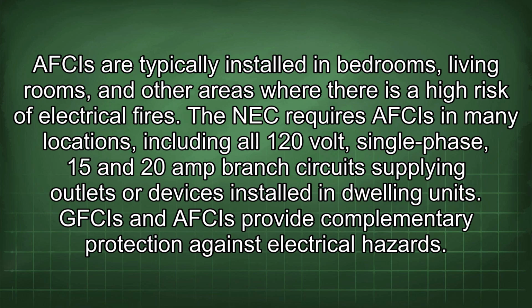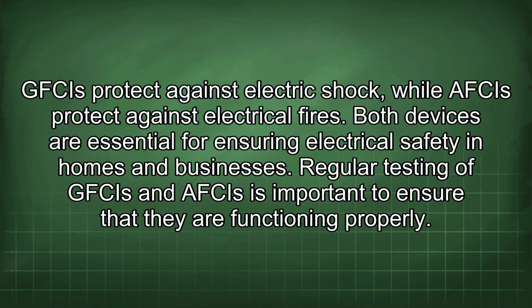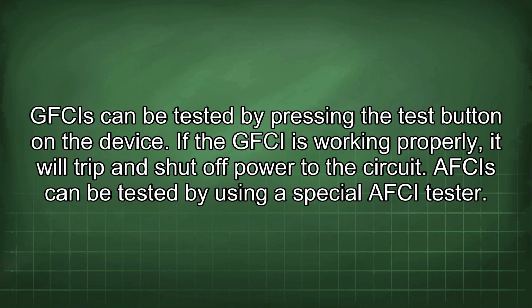GFCIs and AFCIs provide complementary protection against electrical hazards. GFCIs protect against electric shock, while AFCIs protect against electrical fires. Both devices are essential for ensuring electrical safety in homes and businesses. Regular testing of GFCIs and AFCIs is important to ensure that they are functioning properly. GFCIs can be tested by pressing the test button on the device. If the GFCI is working properly, it will trip and shut off power to the circuit.